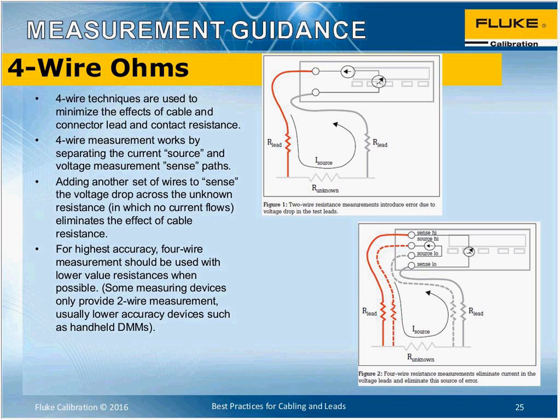And so this 4-wire method allows you to source the current, but then take a separate measurement, or sense the resistance or voltage across the load, to give you a resistance measurement that does not account for the lead. So it's not even paying attention to the resistance of the lead, so it's not included. So it's a very good method for making resistance measurements.